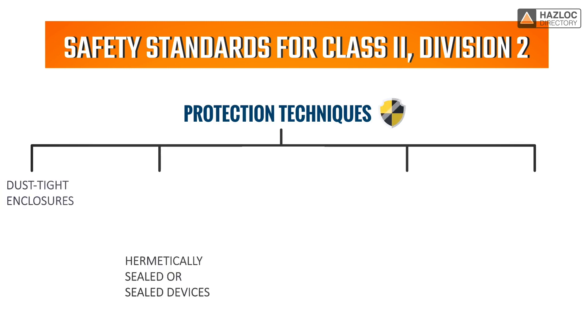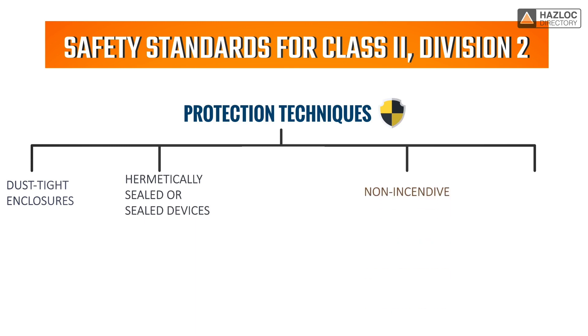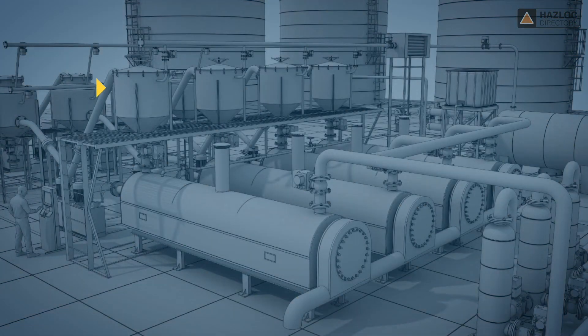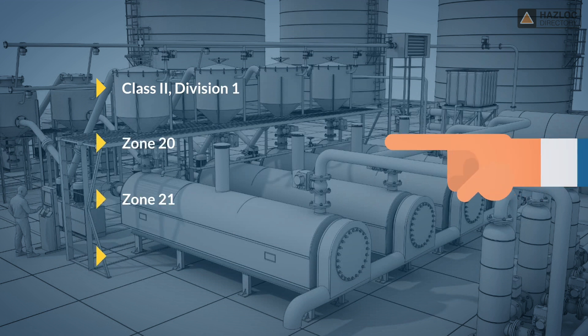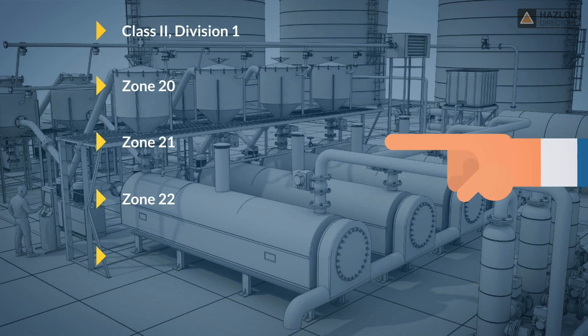The protection techniques include dust-tight enclosures, hermetically sealed or sealed devices, non-incentive, and purging and pressurization type Z. Also, equipment that is suitable for use in Class 2 Division 1 and Zone 20, 21, or 22 in North America is permitted to be installed in a Class 2 Division 2 area.